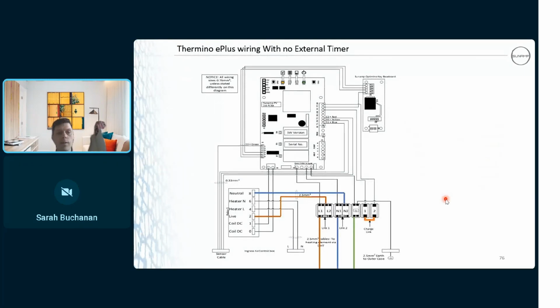So with no external timer, what you'll notice here is LED D5. You turn on, you've got your power, the element is active. When you get a demand, LED D5 will be illuminated, and that will then energize your DC coil here. That will be 12 volts DC coming out here, which energizes your coil. Your power is coming in, up to here, powering up the PCB. But we're also linking that power across to L2, and that goes to this connection of your relay. If you energize that relay, it closes the contact, which sends power down to your element. All right.